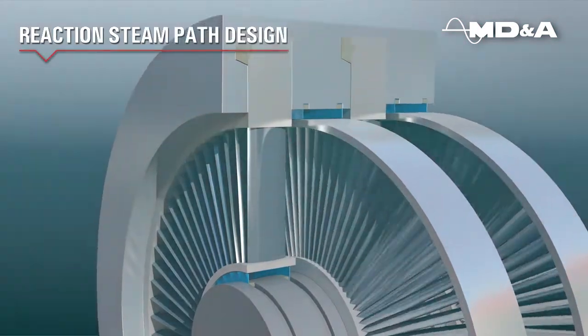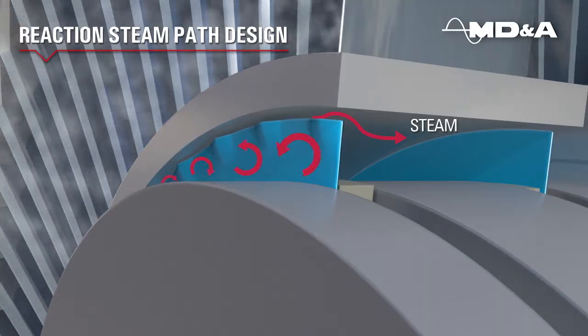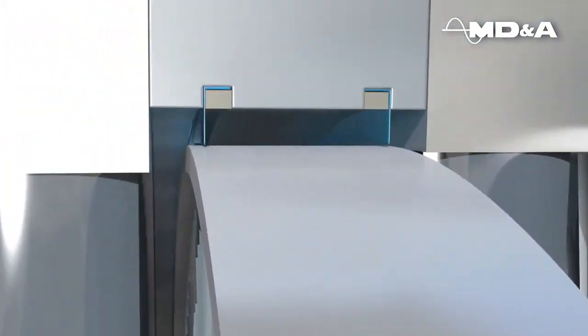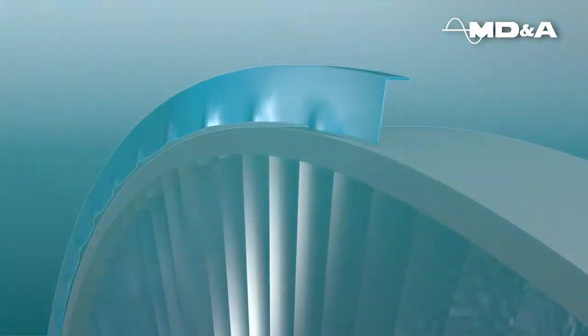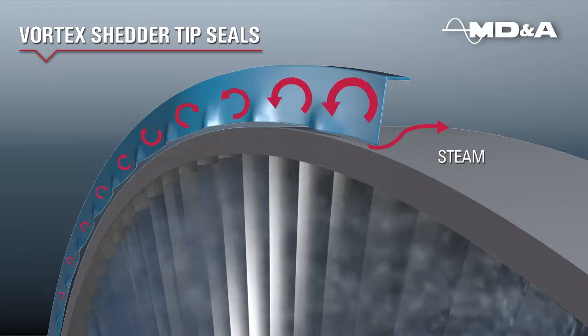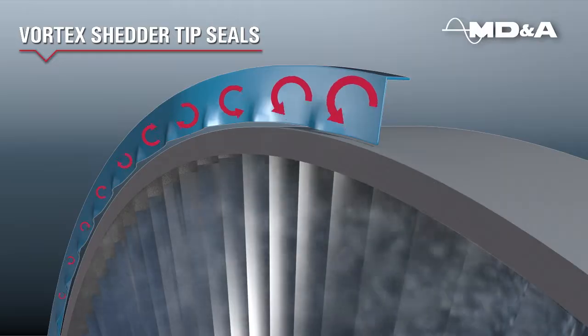The Vortex Shedder also operates on a reaction steam path design, where it can be applied to the rotating seal strip and the stationary seal strip. These vortices increase the pressure drop, resulting in lower flow and less leakage across the seal, translating to improved stage heat rate performance for the steam turbine.